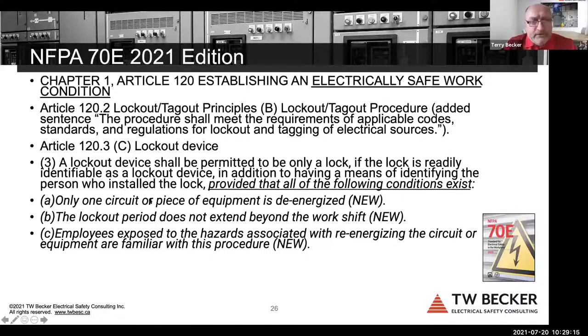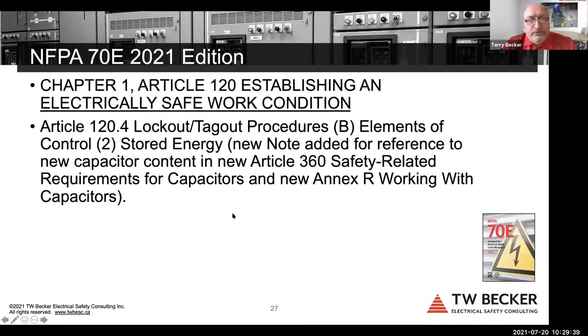So this relates to adding some language that a lockout device can be only a lock without a tag, but you have to have this information in place. So these are new items, just again, little tweaks here and there. This one's unique. The locks have been provided without a tag, but then the lock has to have some unique identification on it. And it lists 3 other requirements here when that's the case. Elements of control. So establishing electrically safe work condition, 120.4, stored energy. So a new note was added that correlates to this new Article 360 related to capacitors.